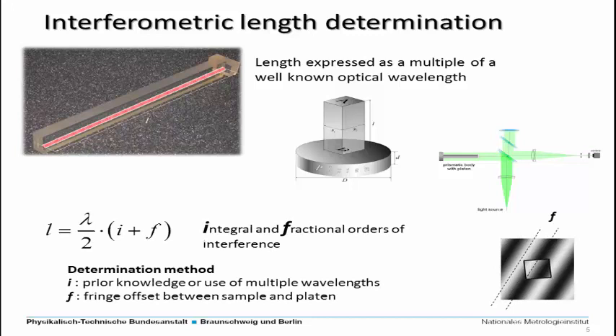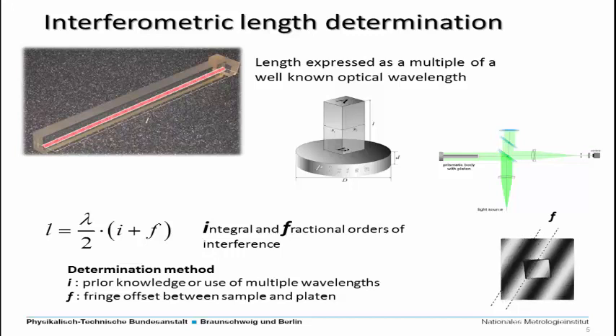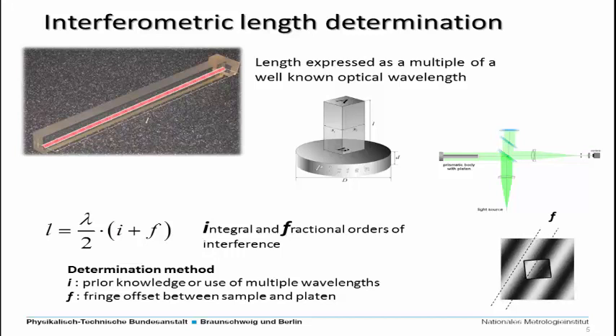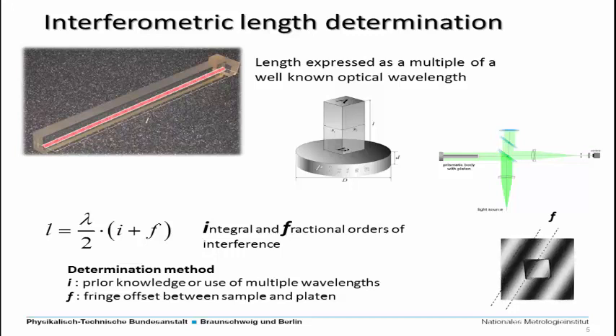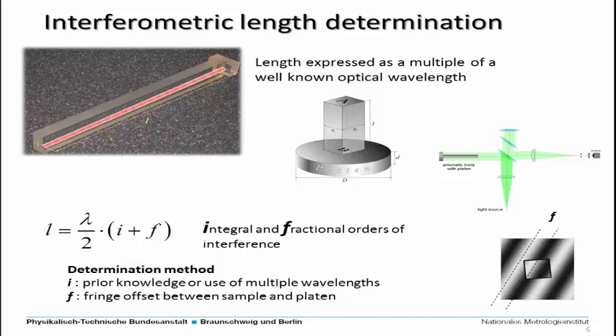And the length can then be defined as it is stated over there, as a multiple of half the wavelength multiplied by the sum of an integral and a fractional order of interference. So what we are determining is this gap here in this simulated interferogram, the gap between the interference pattern on the surface of the sample body and the surface of the reference plate on which the sample under test is located.